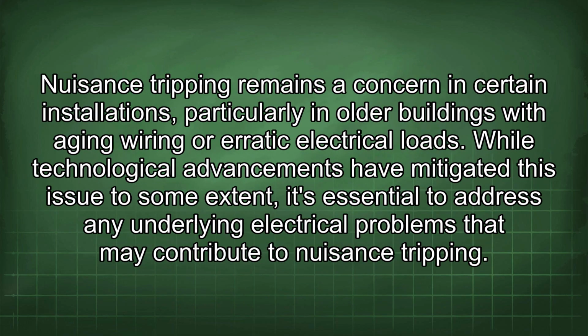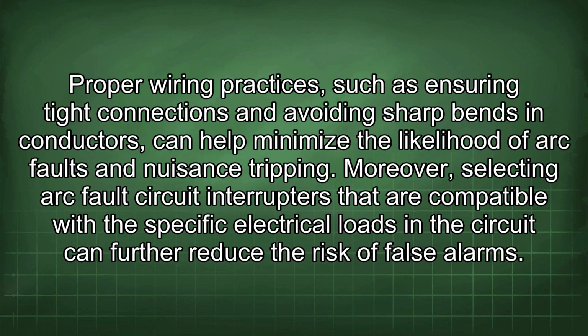Nuisance tripping remains a concern in certain installations, particularly in older buildings with aging wiring or erratic electrical loads. While technological advancements have mitigated this issue to some extent, it's essential to address any underlying electrical problems that may contribute to nuisance tripping. Proper wiring practices, such as ensuring tight connections and avoiding sharp bends in conductors, can help minimize the likelihood of arc faults and nuisance tripping. Moreover, selecting arc fault circuit interrupters that are compatible with the specific electrical loads in the circuit can further reduce the risk of false alarms.